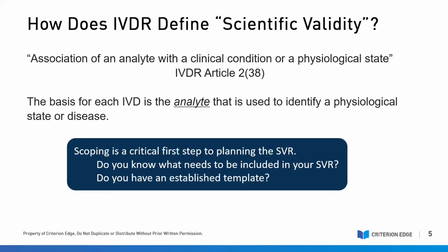The IVDR guidance recommends that you should plan how to demonstrate that scientific validity of the analyte as early as possible in your development cycle. However, the SVR is a new requirement, so it's still not 100% sure what the expectations are to establish scientific validity of the IVD under evaluation. While we all await notified body feedback to clarify the level of detail expected, we should start by just relying on the extensive experience from the medical device world in order to develop a process and a framework to start to build off of.